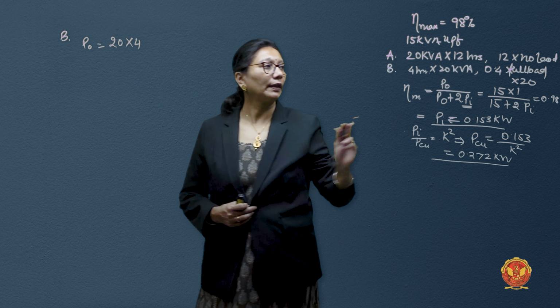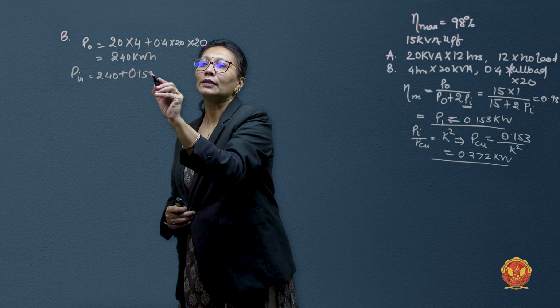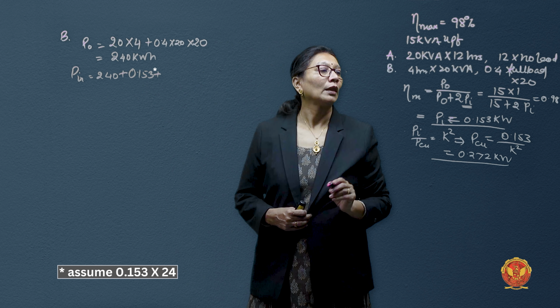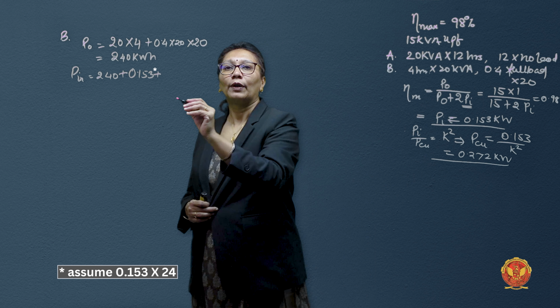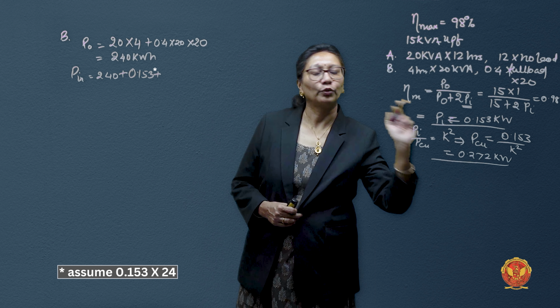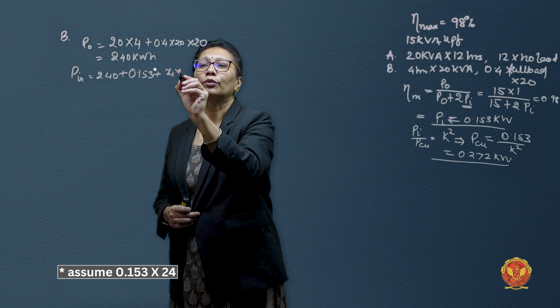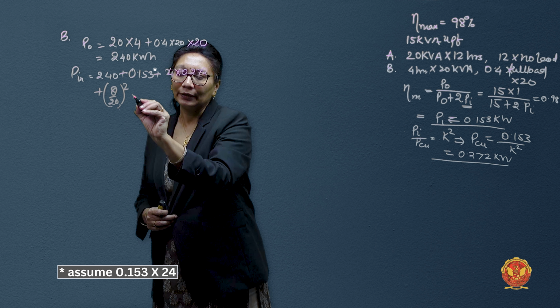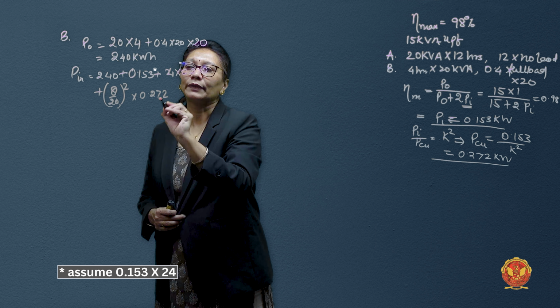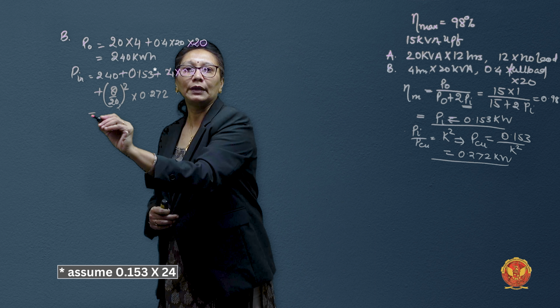Now what do we have to find? The input power. For input power, first of all 240 plus iron losses 0.153 into 24, plus copper losses. We have 20 kVA for only 4 hours and 0.4 of full load for the remaining. So first 4 into 0.272, plus (8 by 20) whole square into 0.272 for the remaining hours, that is 20 hours.